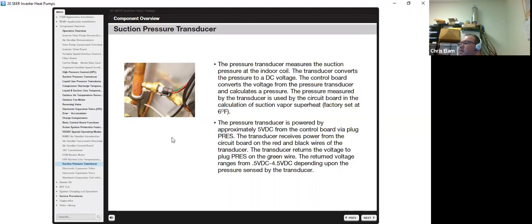The pressure is measured on the circuit board in the calculation of the suction vapor superheat at approximately 6 degrees. The pressure transducer is powered by approximately 5 volts DC. The transducer receives power from the circuit board on the red and black wires of the transducer. The transducer then will return the voltage back via the green wire. The voltage returned will be anywhere between 0.5 and 4.5 volts DC, depending upon the pressure that is sensed. And this is basically what you have in a transducer. These are 3 wires. So not much to it.